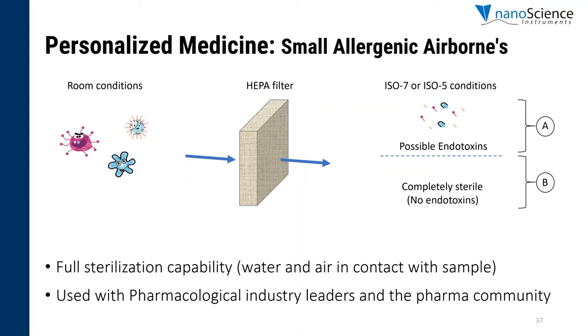Why is this important? When electrospun fibers or electrospray particles are designed for a specific patient, that patient may be allergic to some allergens that could be present during sample development. Thus, sample development for personalized medicine can be implemented with the Fluidnatek if we do a total sterilization of the water, the air, and use proper configurations of HEPA filters. So if you're working in tissue engineering or the pharmacological area, this might be of interest to you.